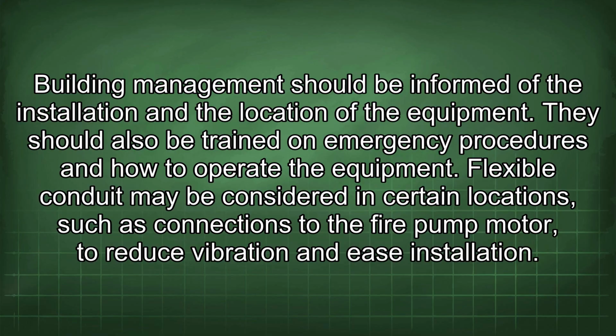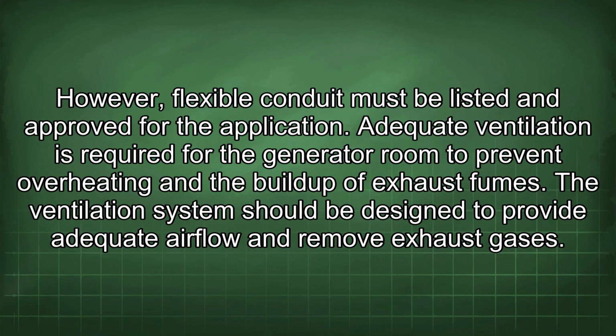Flexible conduit may be considered in certain locations, such as connections to the fire pump motor, to reduce vibration and ease installation. However, flexible conduit must be listed and approved for the application. Adequate ventilation is required for the generator room to prevent overheating and the buildup of exhaust fumes. The ventilation system should be designed to provide adequate airflow and remove exhaust gases.